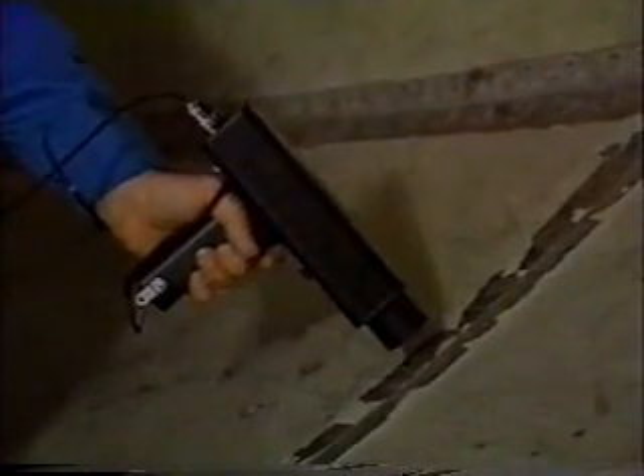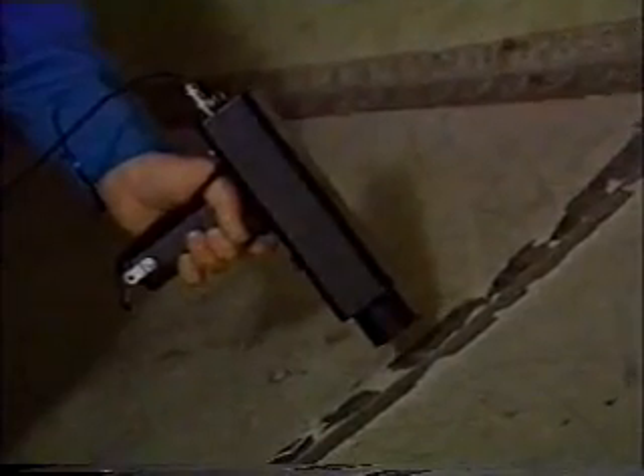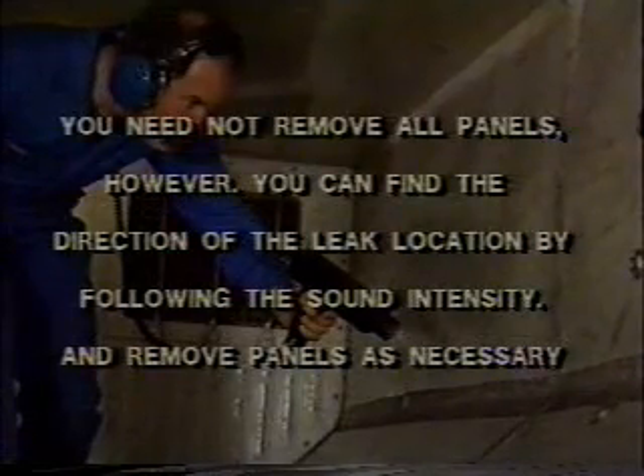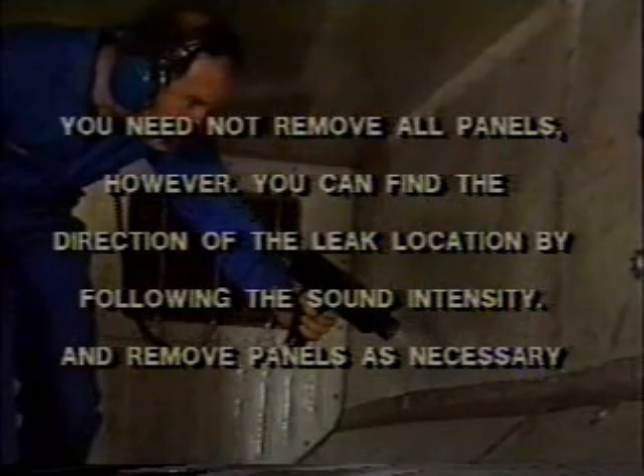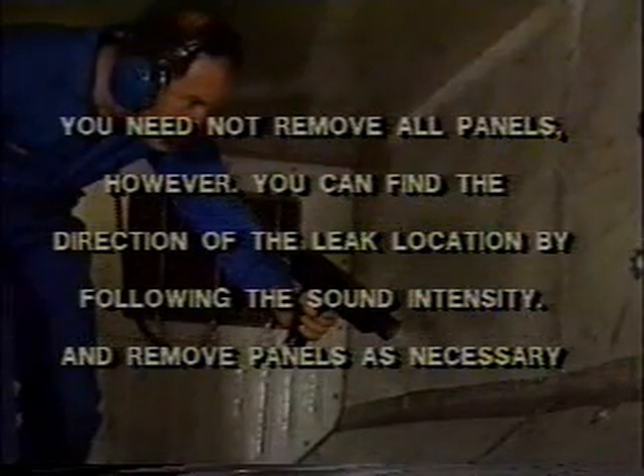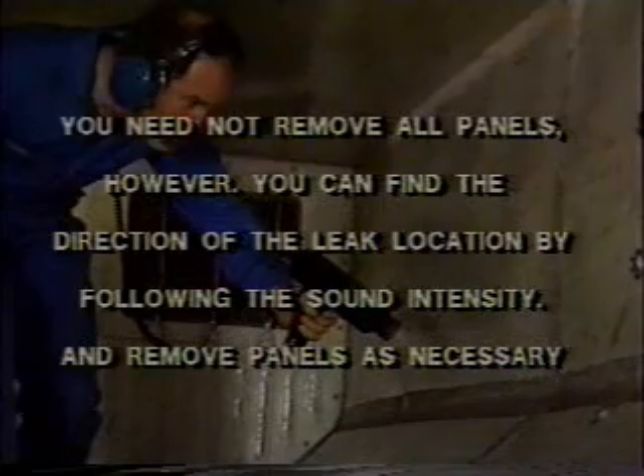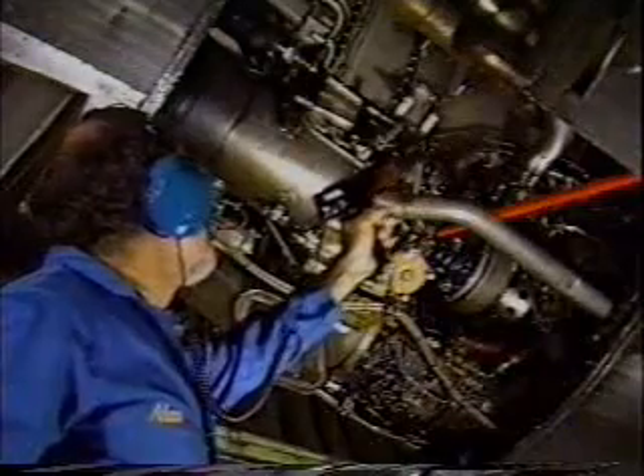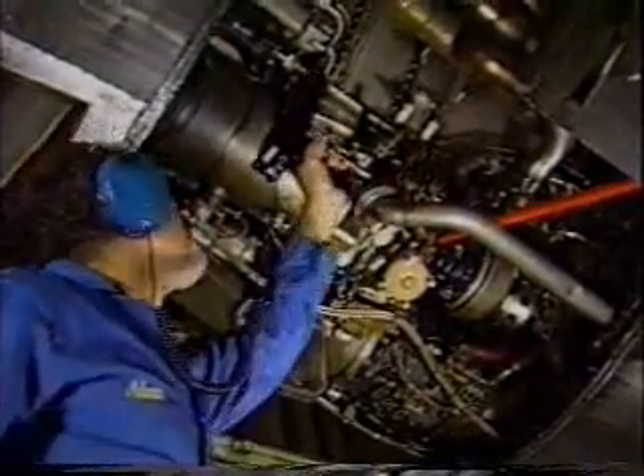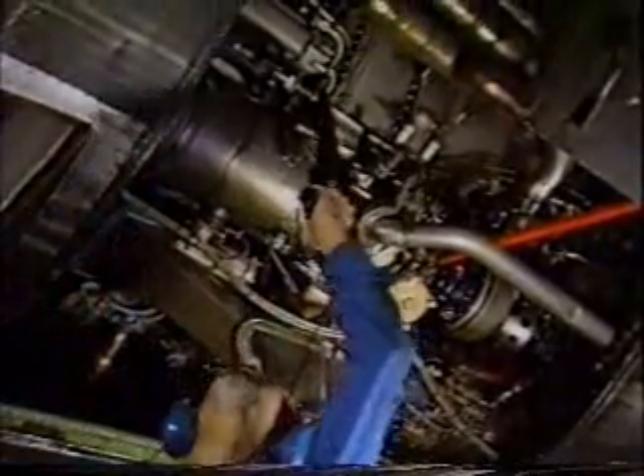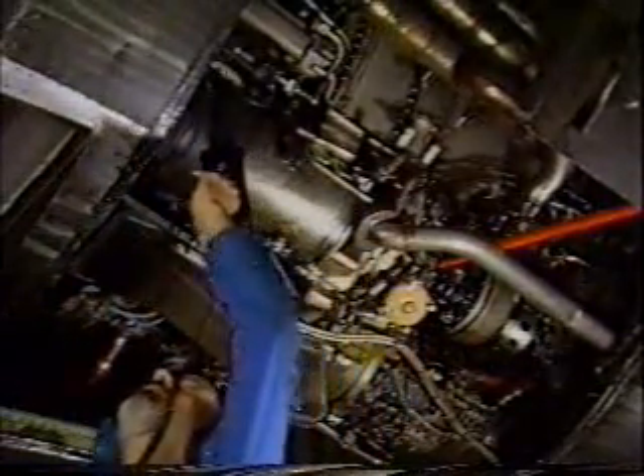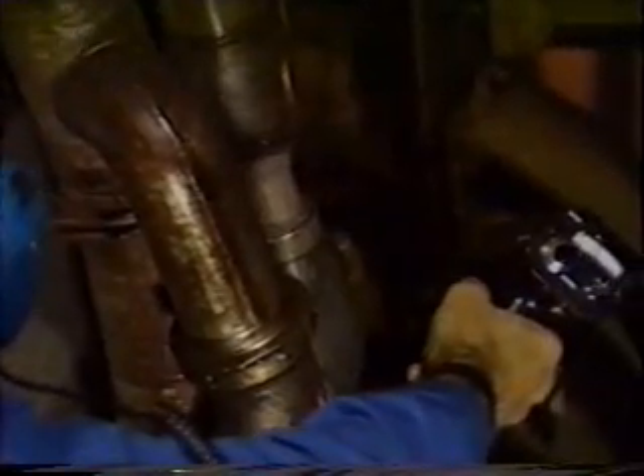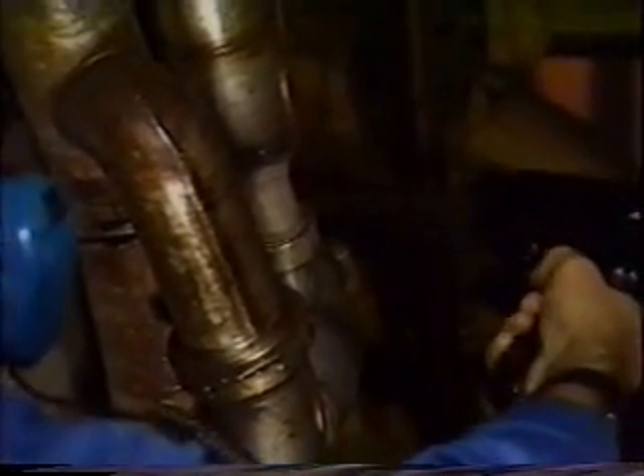If a leak is behind a panel, only gross signals will be heard. Check for leakage whose signals may be blocked. Some panels must be removed before scanning is completed. You need not remove all the panels, however. You can find the direction of the leak location by following the sound intensity and removing panels as necessary. Because mechanics can check equipment from a safe distance, the ultraprobe minimizes the risk of being burned while testing hot sections of pneumatic duct. De-icers may also be checked for leakage.